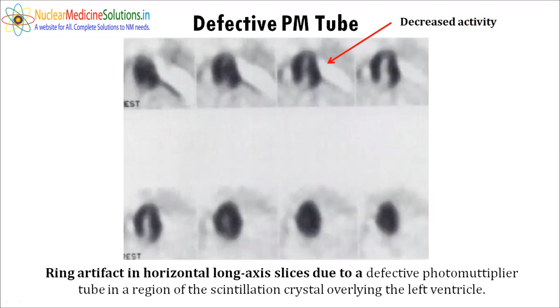If there is any defective PMT tube present in your gamma camera, it will also produce a cold area in your uniformity image, or it will affect your uniformity, which can be seen here. Because of the defective PMT in the gamma camera, it is showing a ring artifact in the horizontal long axis. You can see here, it disappeared after replacing the PMT tube of that gamma camera. This is the second example.